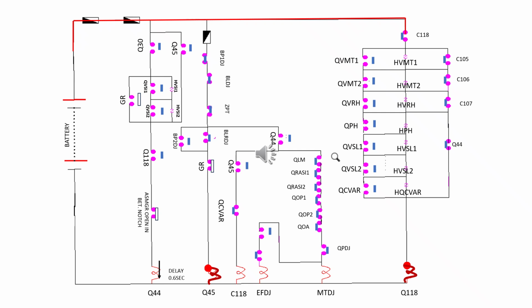When Q45 is energized, its contact will make in the Q44 branch. You see the first branch on the top, there is a Q45 contact. When the Q45 relay energizes, it will close the Q45 contact on the first branch on the top, and from there it will come. Q118 is already energized.